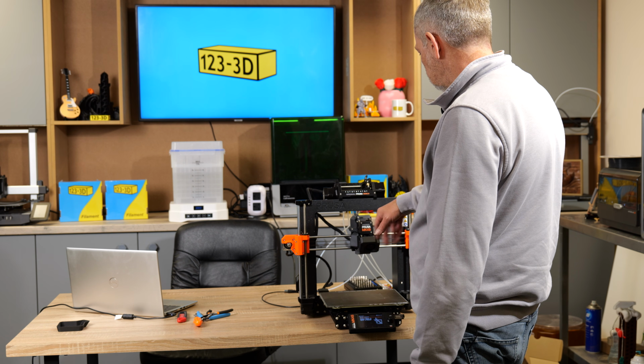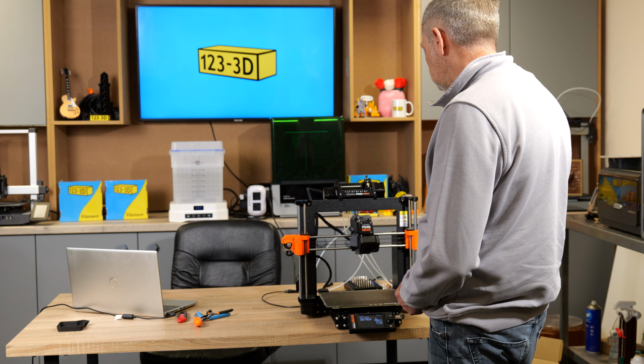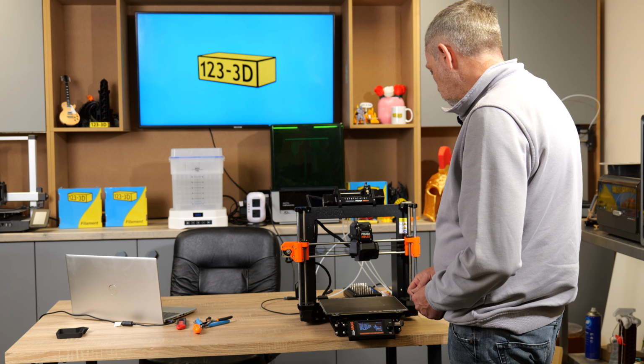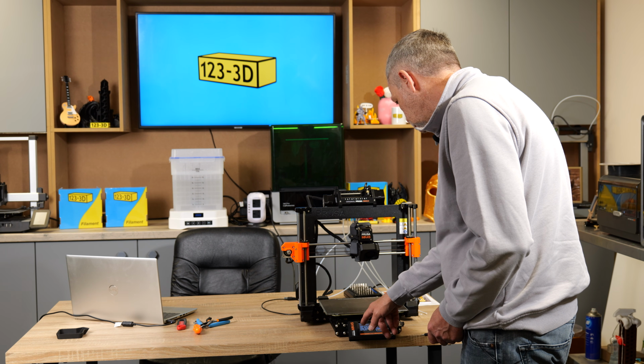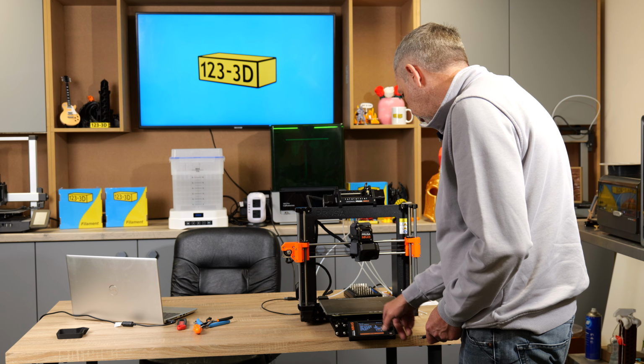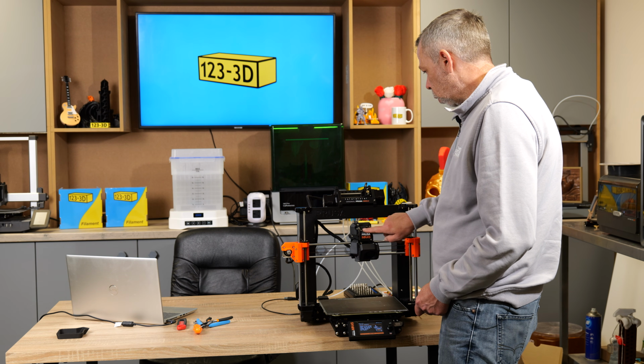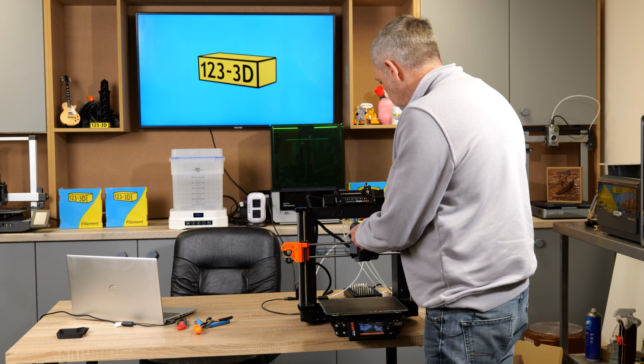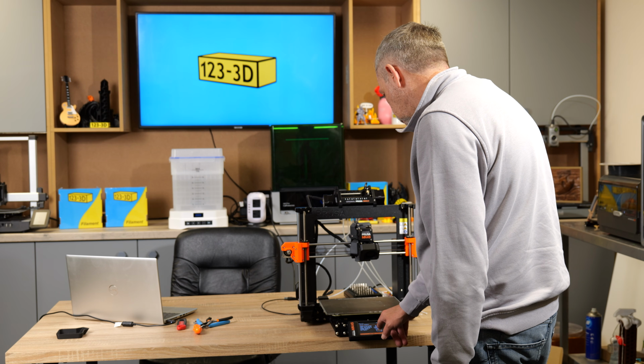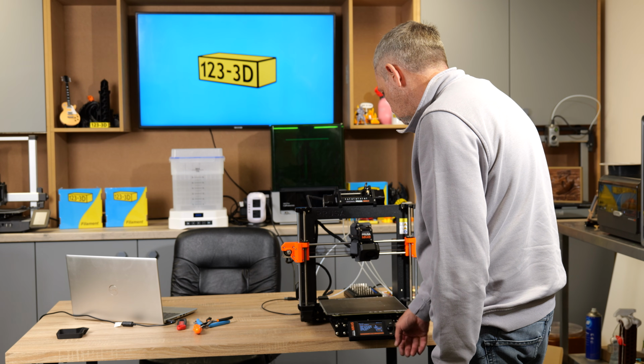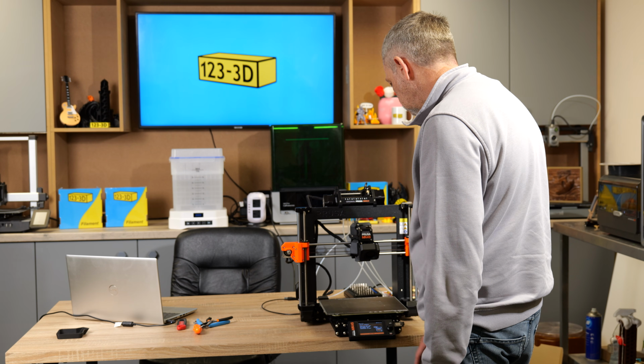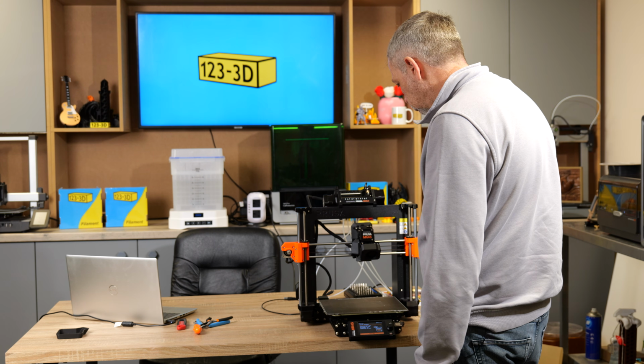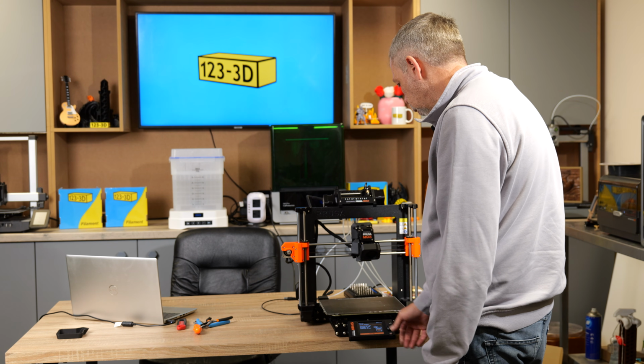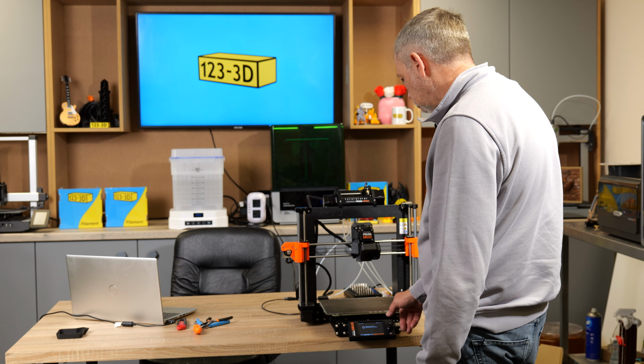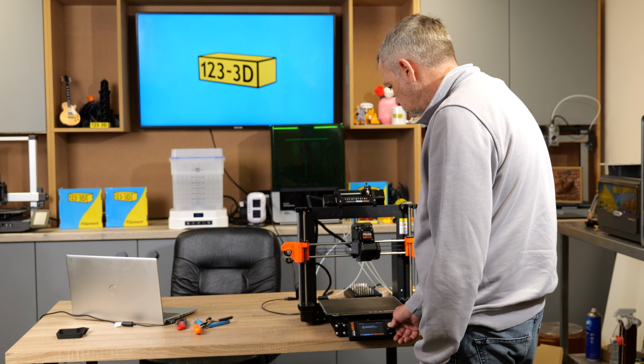Continue. The gearbox will rotate. Please wait approximately 20 seconds. Okay, tighten the M3 screws firmly in the correct order as shown. So it shows me 1, 2, 3. Just tighten them back down and do not over tighten. So we definitely do not want to over tighten. Click continue, put the lever back, lock that into place. Calibration is done. Continue. Continue running calibration and tests. We don't need to do that, so we should quit.